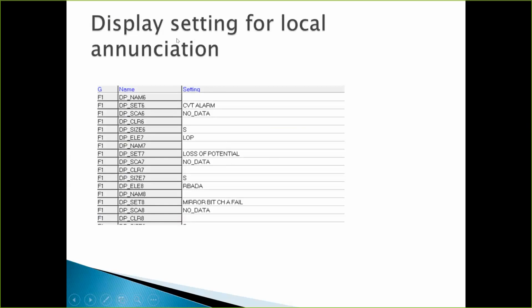I need a display point for our local annunciation, okay? If the CVT that feeds this relay is in alarm, I want to display that, okay? So if that equation was satisfied, I see a CVT alarm on the rolling display of that specific relay, that specific line. And that's how that tells the operator when he gets there, hey, this is the line that's in trouble. This is the one I need to look at, okay?